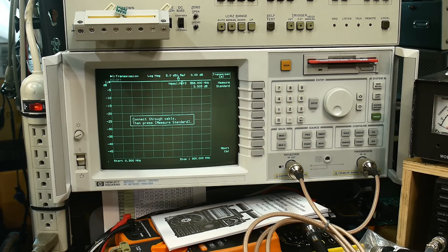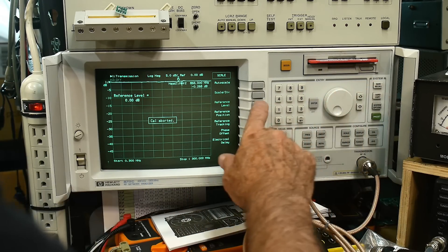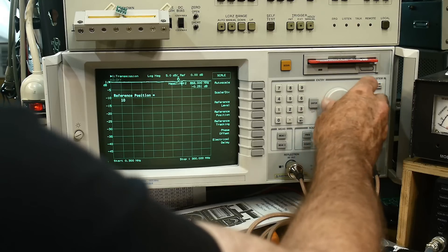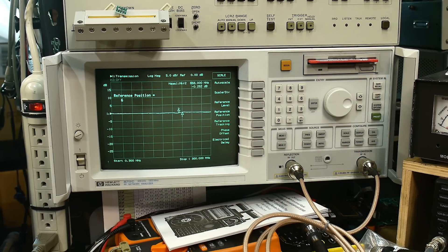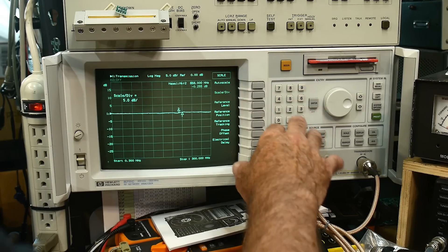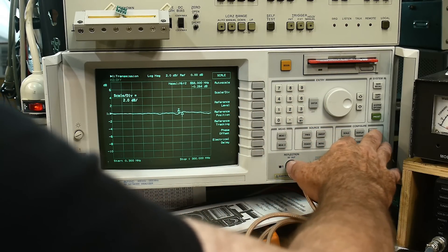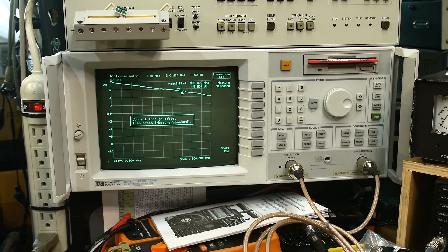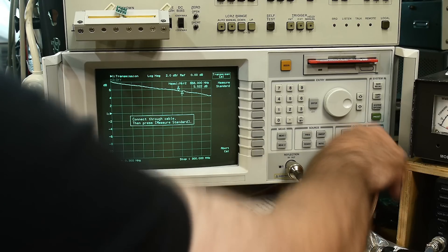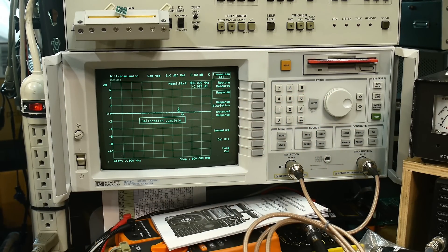And we will set the reference position to maybe in the middle. There we go, and we'll do a scale of, I don't know, let's say 2dB per division. Let's do a cal again. Connect through cable, and there we go. Look at that straight, straight, straight line.